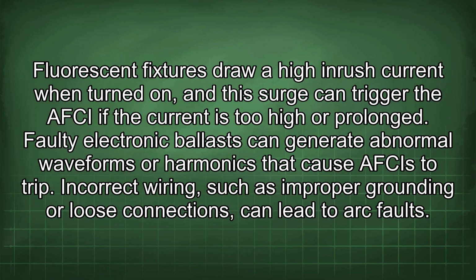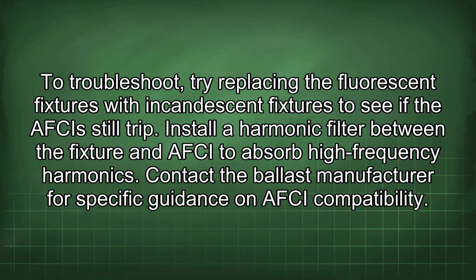Faulty electronic ballasts can generate abnormal waveforms or harmonics that cause AFCIs to trip. Incorrect wiring, such as improper grounding or loose connections, can lead to arc faults. To troubleshoot, try replacing the fluorescent fixtures with incandescent fixtures to see if the AFCIs still trip.